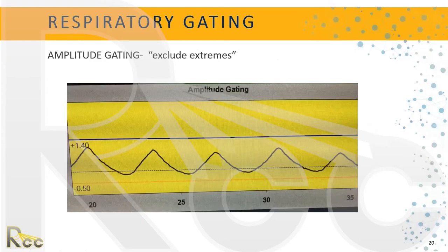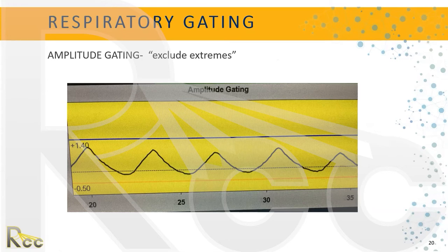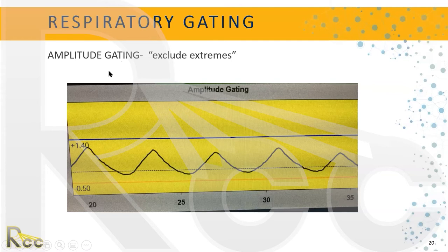An extreme example is free breathing with a very wide threshold — we're still using gating but aren't particularly concerned about inspiration or expiration amplitude. However, we do want the beam to turn off if the patient coughs, yawns, or does anything that causes an extreme change in breathing. Without gating, if a patient coughs at the LINAC, we usually don't have time to hit the off button. The gating software turns the beam off for us automatically.